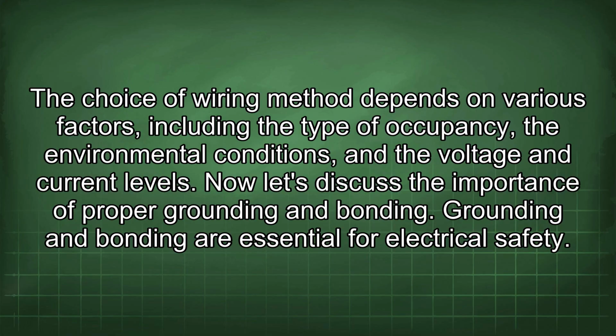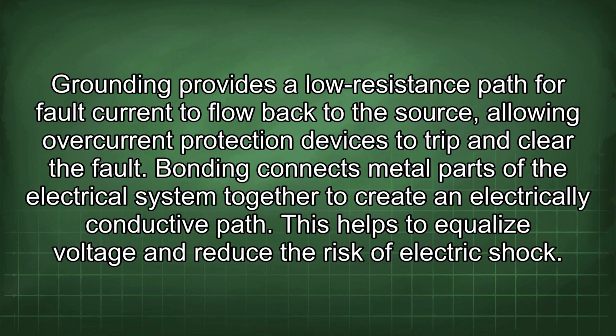Grounding and bonding are essential for electrical safety. Grounding provides a low-resistance path for fault current to flow back to the source, allowing overcurrent protection devices to trip and clear the fault. Bonding connects metal parts of the electrical system together to create an electrically conductive path. This helps to equalize voltage and reduce the risk of electric shock.